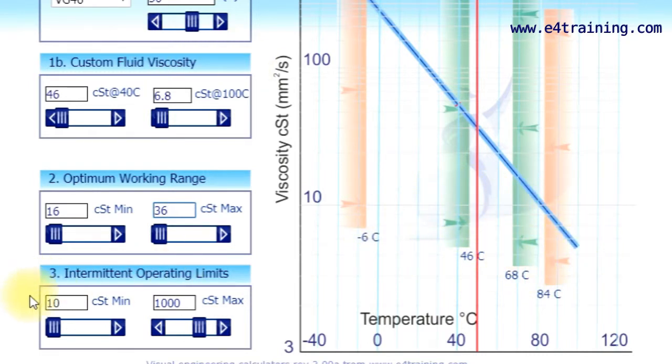We also have on the pumps an intermittent operating limit specification, 10 to 1000 centistokes. You can run at 1000 at startup and it won't destroy the pump, but certainly you can't run for long periods like this. It's just purely to start or very short periods at high temperature. So you don't want to be in these regions, but that's the absolute limit which is often useful.